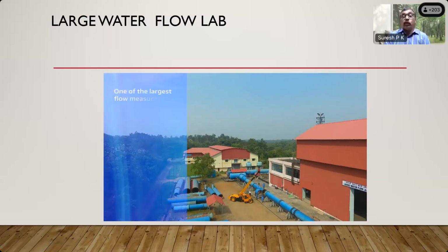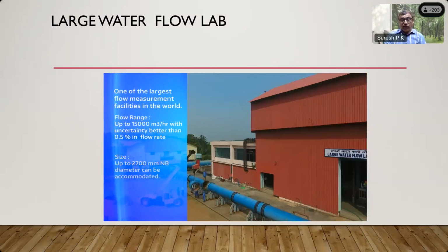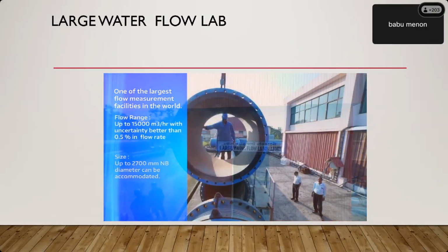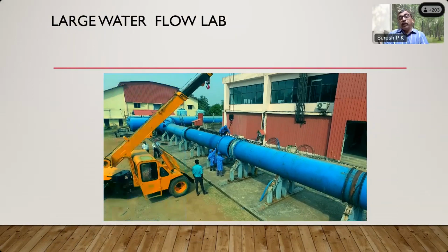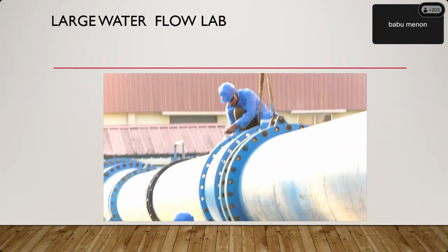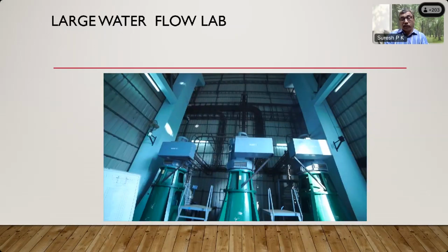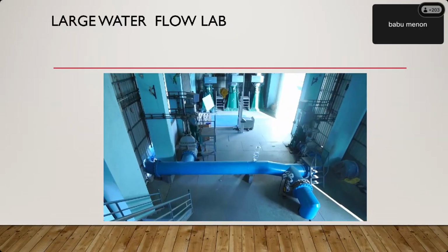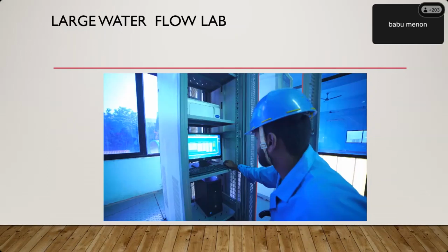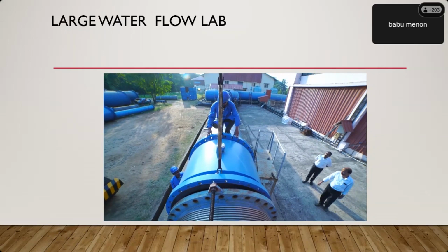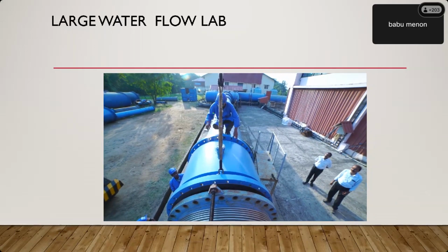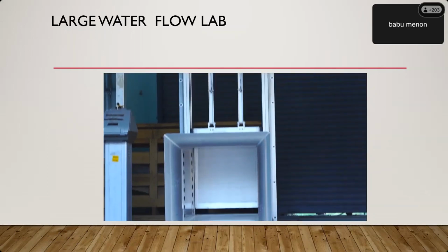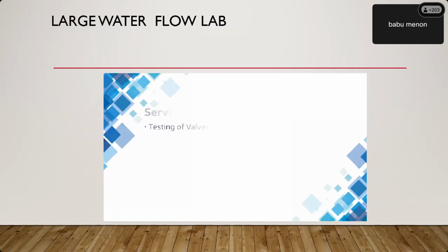Then we have a large water flow lab in FCRI, which uses the master meter calibration method for calibration of flow meters. The uncertainty is low, as you can see, it's 0.5%. You can go up to 3000 mm diameter and a flow rate of up to 15,000 meter cube per hour. These are some of the facilities at FCRI.